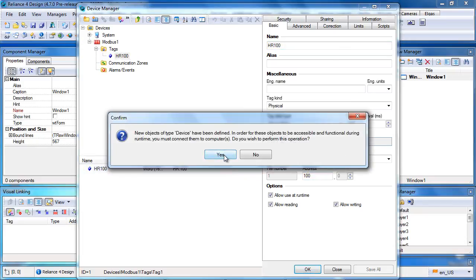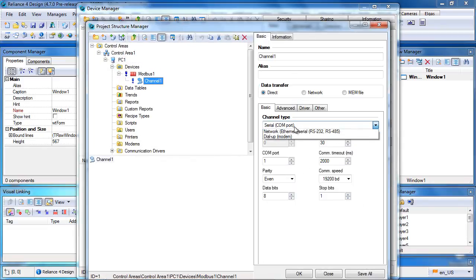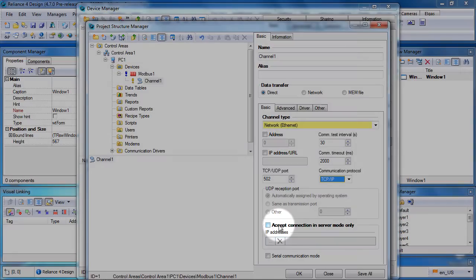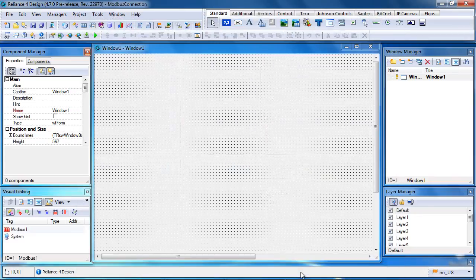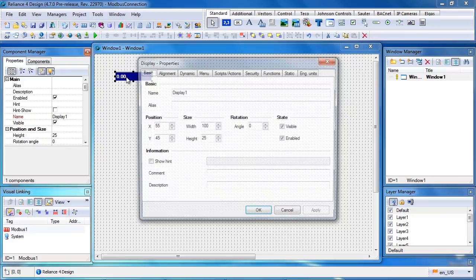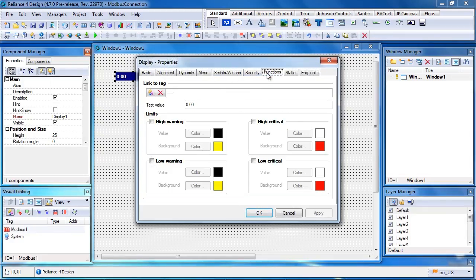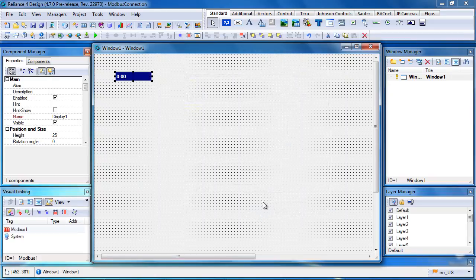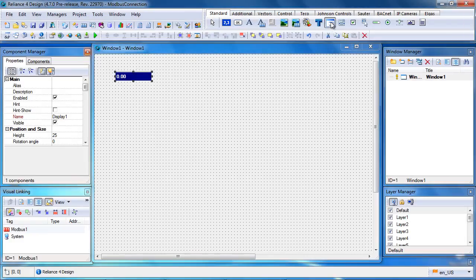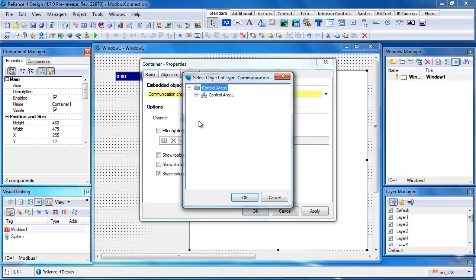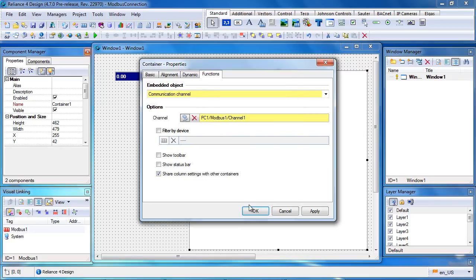Now, let's confirm connecting the device to the computer, choose the Network Ethernet channel type, and set the communication protocol to TCP/IP. This option also allows us to activate the server mode if needed. We must not forget to save the changes. Once the Modbus device is defined, a display component can be added to the visualization window. We must double-click to open the component's property editor and go to the Functions page to specify a link to the tag. To change the tag's value during runtime, we must go to the Security page and activate the 'Enable Setting Value' option. We can also add a container component to the window where we will select the respective communication channel. We do not need the container for communication with the Modbus PLC, but it will allow us to view the communication.